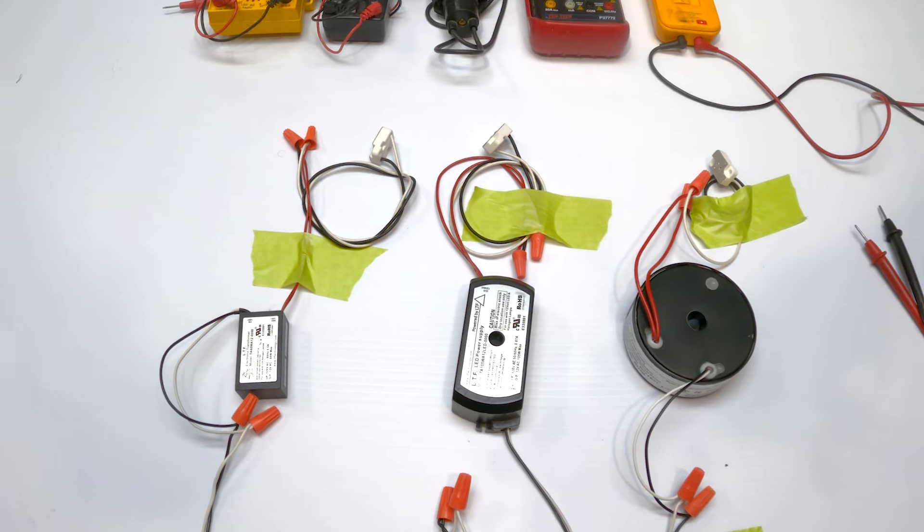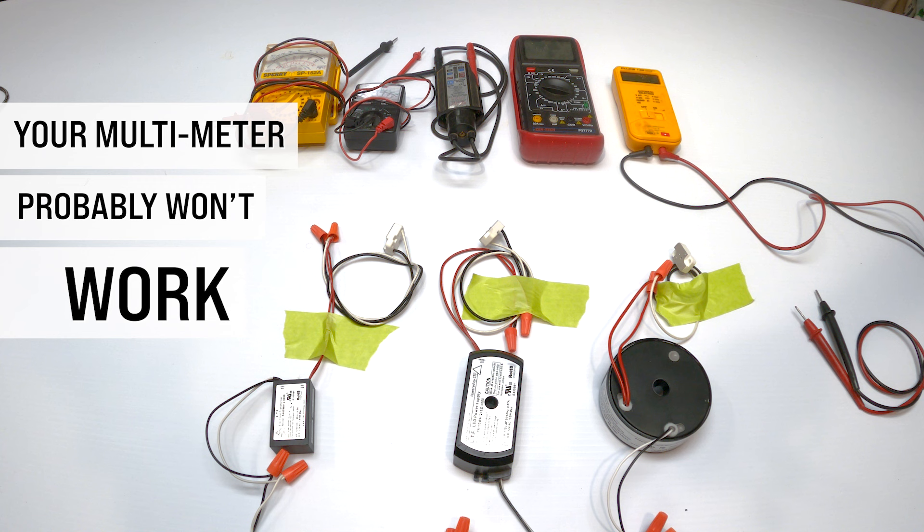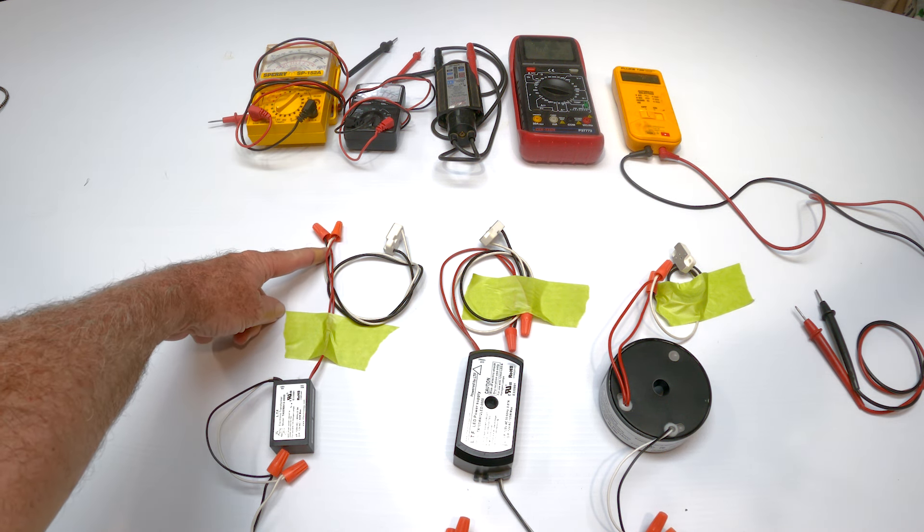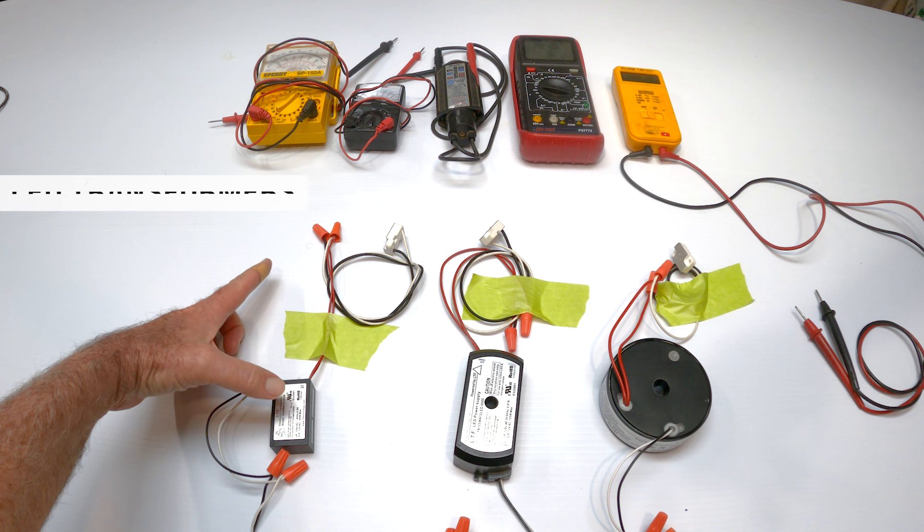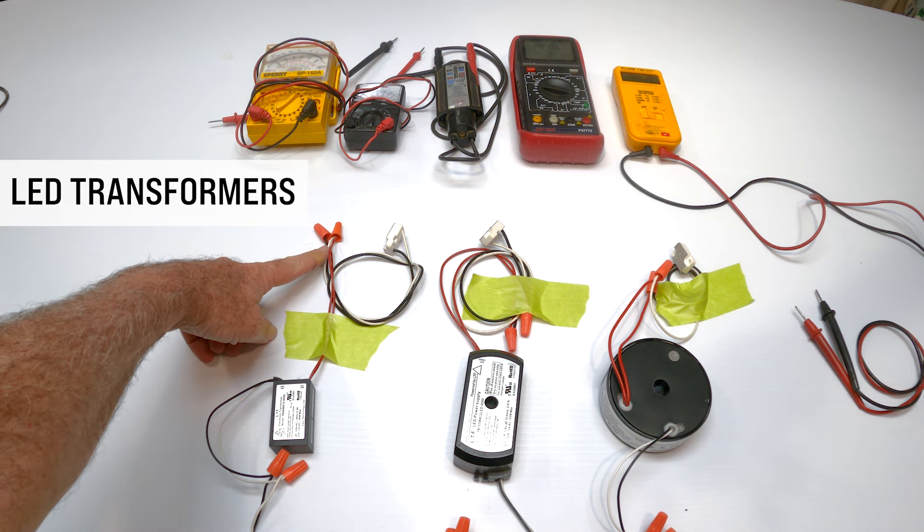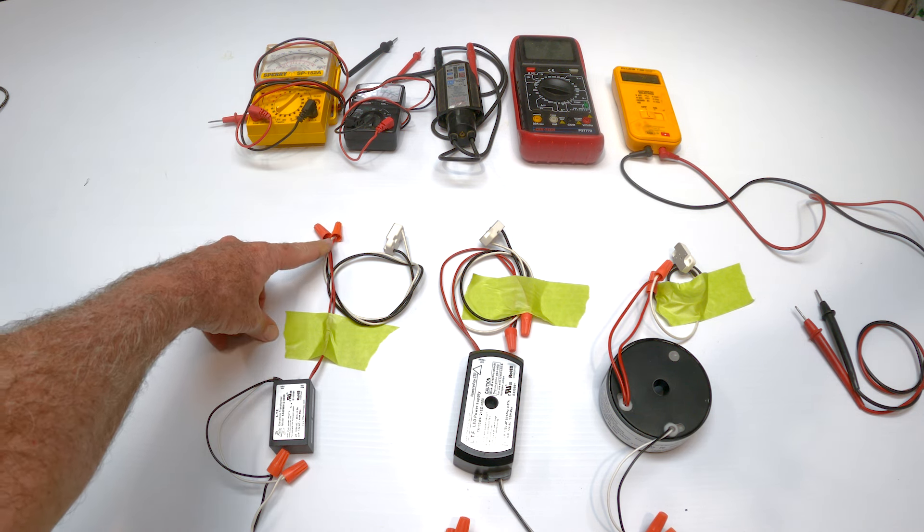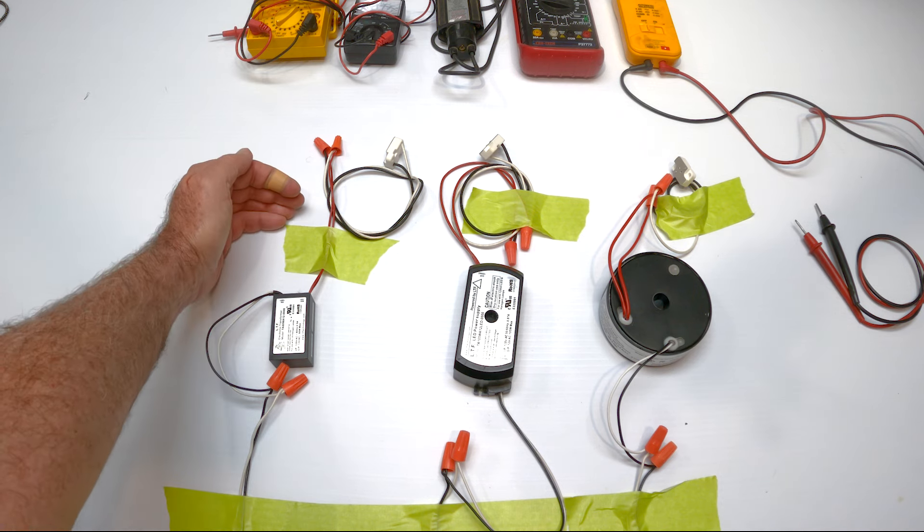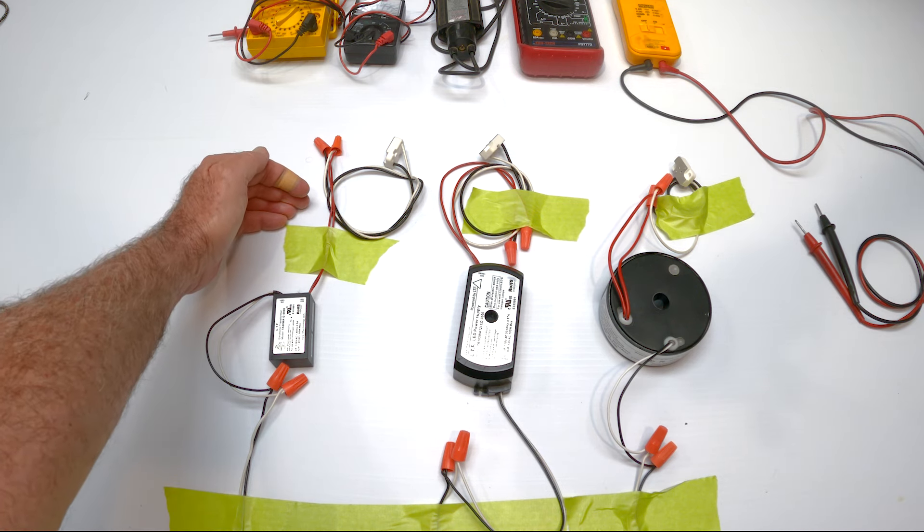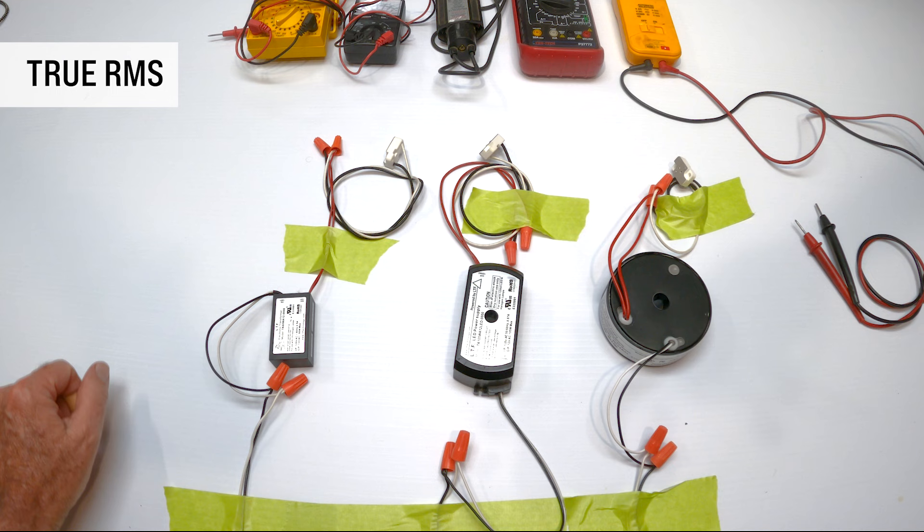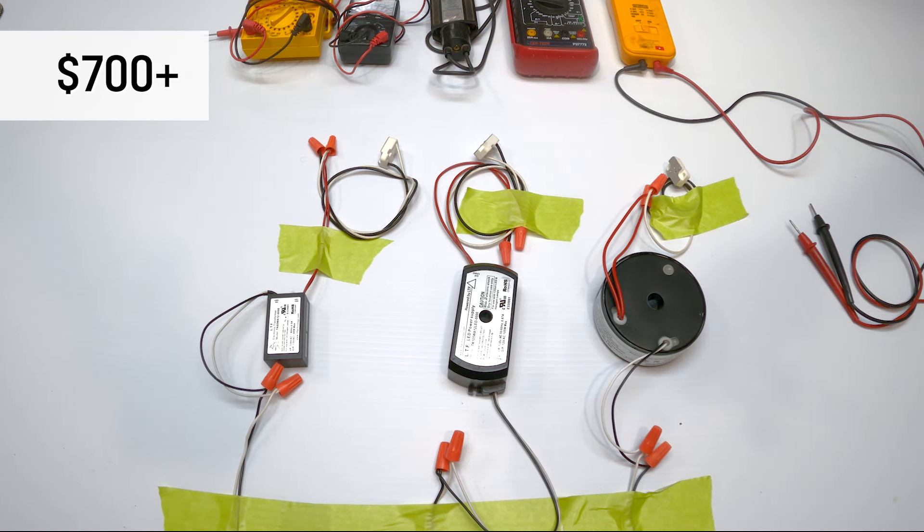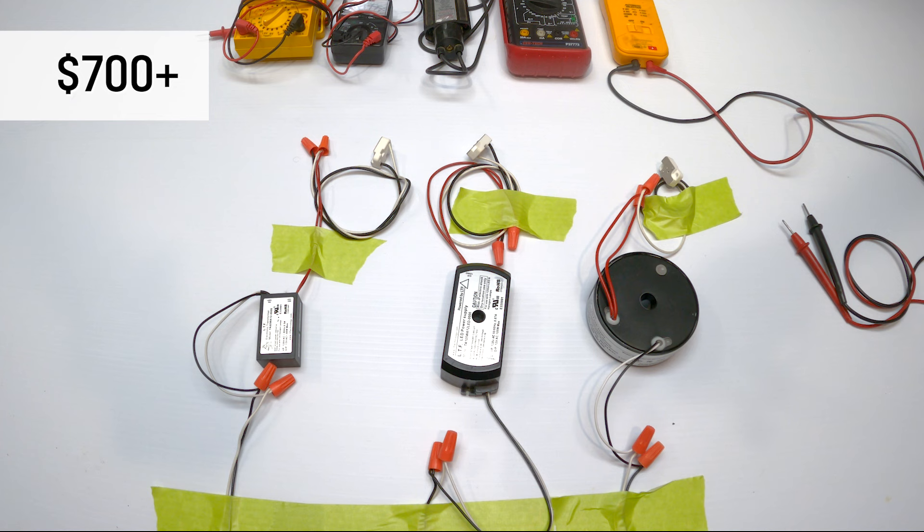This is a great test because none of your voltage meters, most likely, are capable of taking a voltage reading at this point. Because these are LED transformers, you can't use a standard voltage meter to test. You can on the 120 volt side, but on the 12 volt or the 24 volt side, you can't. You need a true RMS multimeter, and they range from about $700 up. So not too many people own those.